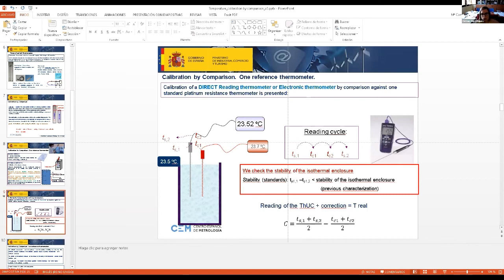Here we have our thermometer under calibration and our standard in the isothermal enclosure. The reading cycle would be: first, we read the standard thermometer, then the thermometer under calibration, then we measure again the thermometer under calibration, and as the last point, we perform a second reading of our standard. Why do we do this? Just to check that the stability of the isothermal enclosure is good enough to perform this calibration with low uncertainty, just to check that our measurement is under control.